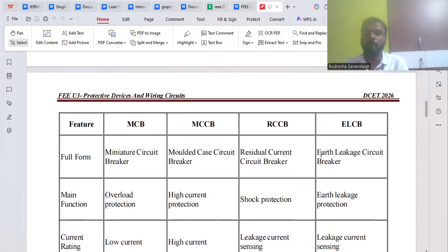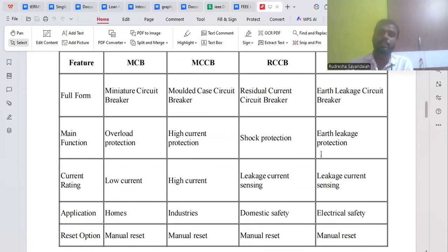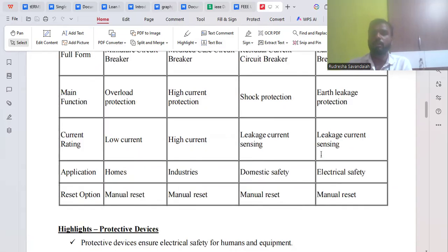Full forms: miniature circuit breaker, molded case circuit breaker, residual current circuit breaker, earth leakage circuit breaker. Main function: overload protection, high current protection, shock protection, and earth leakage protection. Current rating: low current, high current, leakage current sensing. Applications: homes, industries, domestic safety, electric safety. Manual reset.